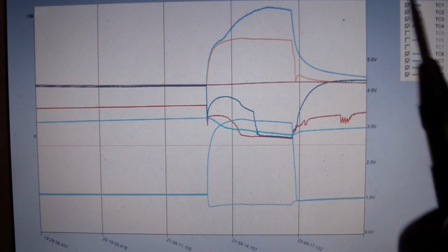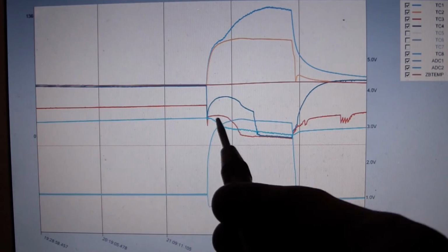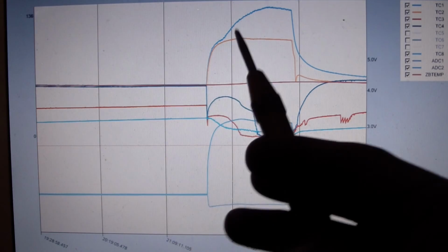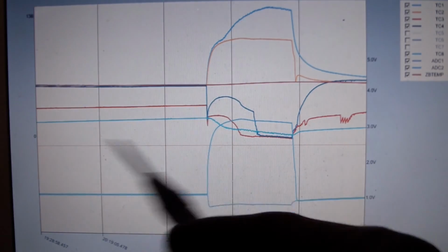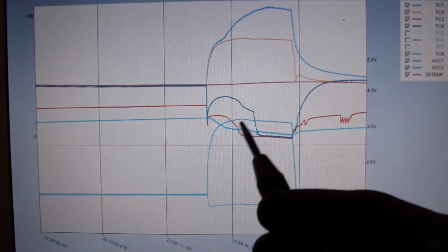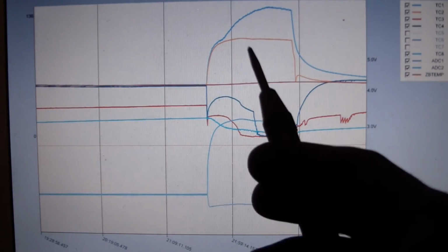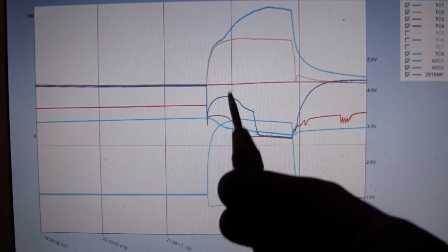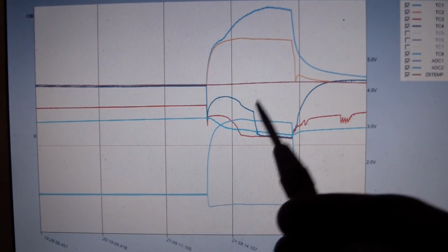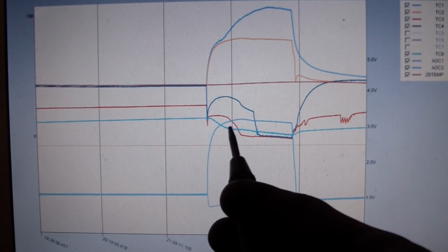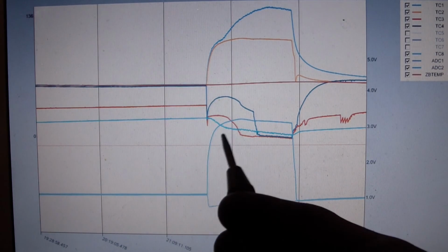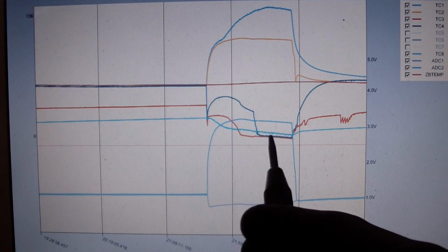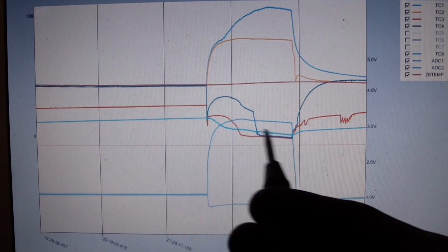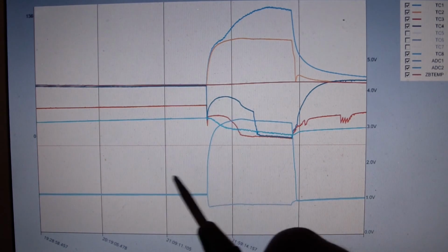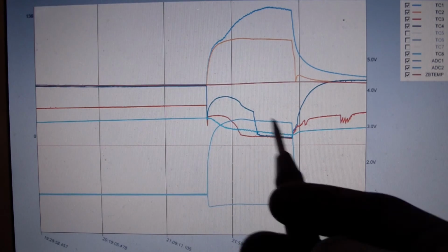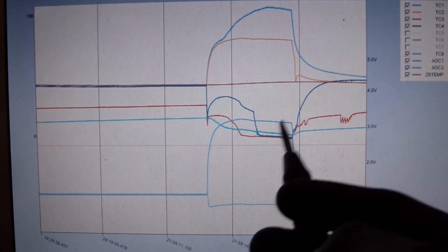level operating conditions. Basically getting that liquid plug as fast as I can by getting low suction temperatures to the compressor as quickly as I can. So increase the mass flow rate to the compressor so I can gain that liquid plug fast, get good mass flow through the capillary tube so I can properly feed the evaporator earlier in the run, rather than having to wait until the conditions of the evaporator change in that all this ice forms around the tubing, reducing the necessary liquid supply from the low side.